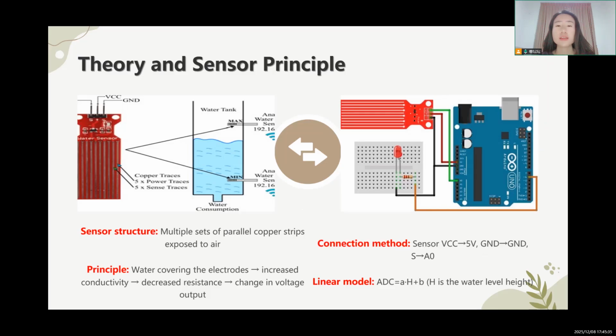A relationship between ADC values and actual water levels was established, and calibration was performed using a linear regression method. During calibration, multiple water level ADC values were recorded, and the fitting formula was ADC equals A times H plus B, where H is the water level height in millimeters, and A and B are calibration constants. The model is simple, effective, and used for calibrating water-conducting sensors in clean water bodies.